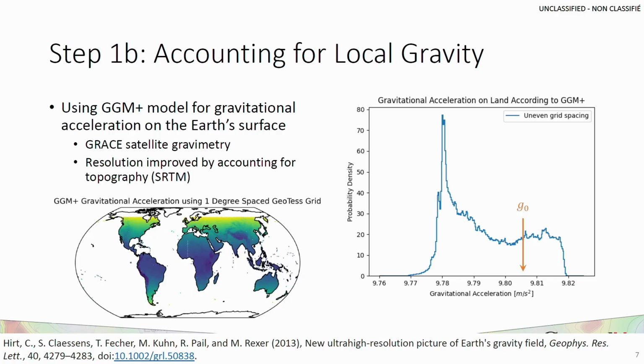To convert the readings to a sensitivity, you need an estimate of the local gravity in meters per second squared. We found a model called GGM+. It stands for Global Gravity Model Plus. It accounts for both the ellipsoidal shape of the Earth and topography. It uses GRACE satellite gravimetry data and Shuttle Radar Topography Mission topography. On the right is a simple histogram of that data. You can see that it varies by about 0.15% to minus 0.35% relative to the standard value of G. If we didn't account for this, it would bias our calibration.